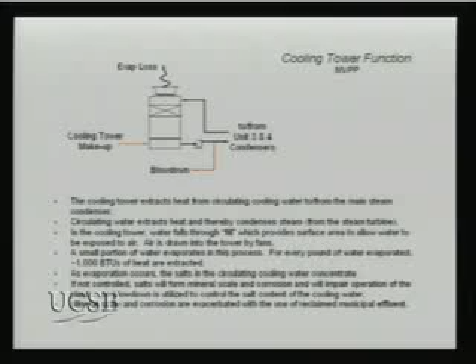Okay, cooling tower. Bob so eloquently described how they work. I'm not going to go into a lot of detail, other than the fact that the issue, again, is that water cycles up in the tower. The term is called cycling up. As you evaporate water, the salts stay behind. It gets more and more concentrated. You have to bleed the tower, and that's called the blowdown.